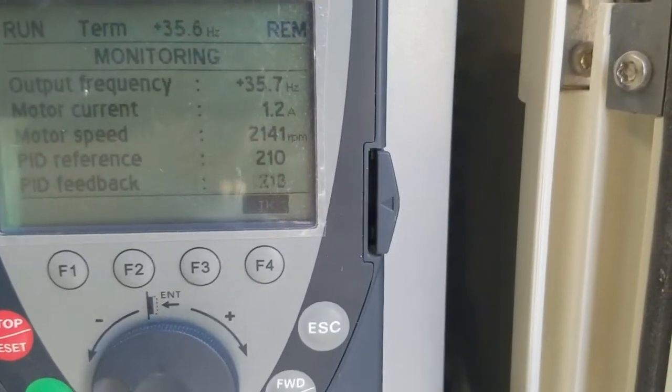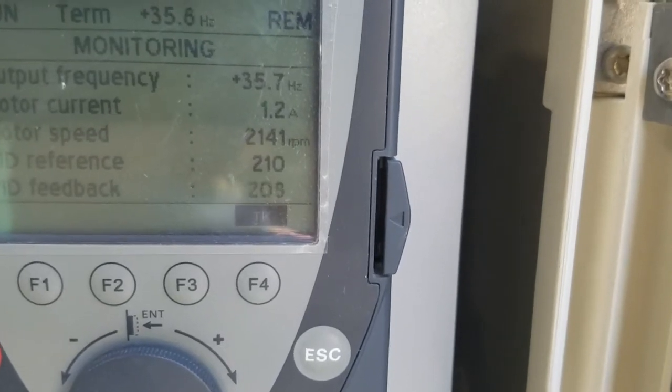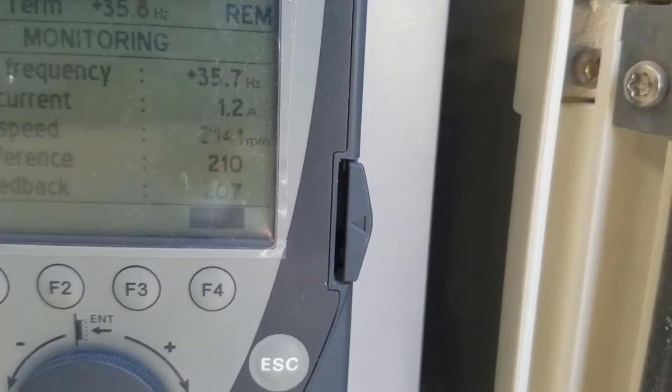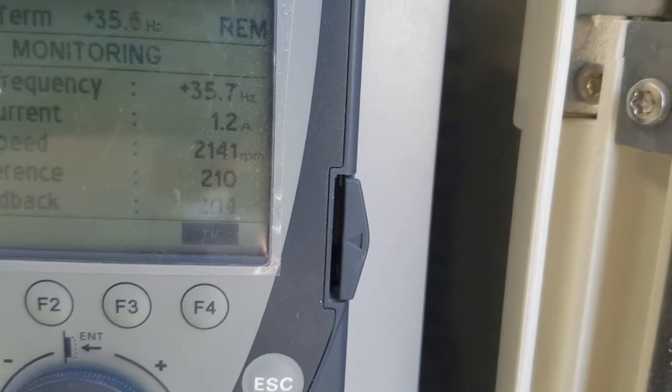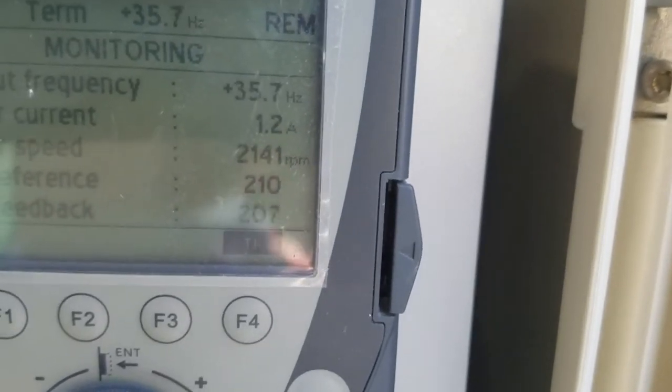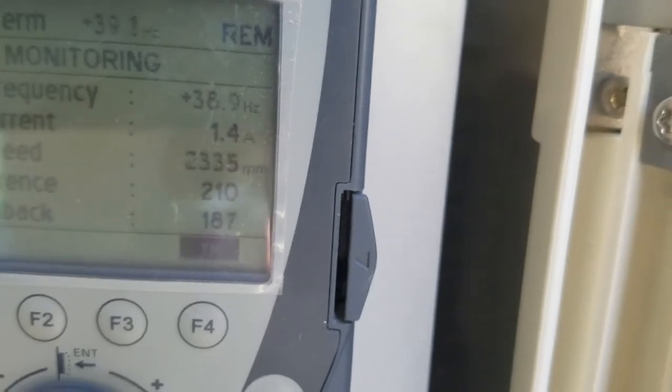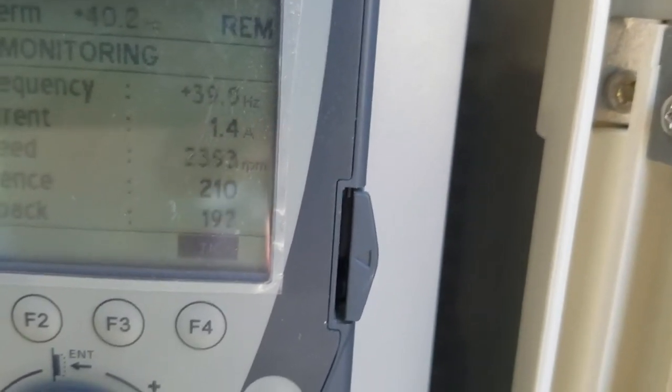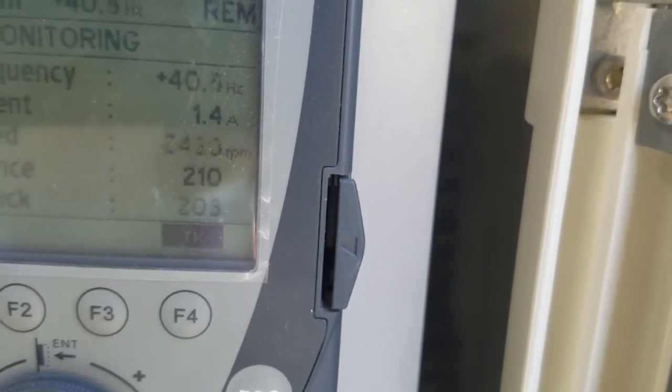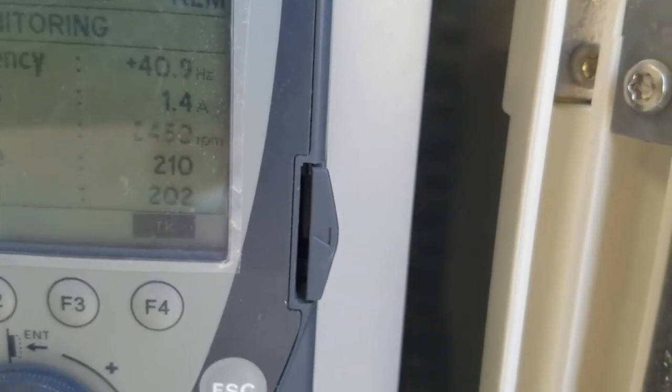Down here you can see the actual pressure, which is around 2.1 bar—that's the lowest line. Now I will open the valve a little bit, and first of all you can hear the sound of the pump running a bit faster. The speed is going to 40 hertz.